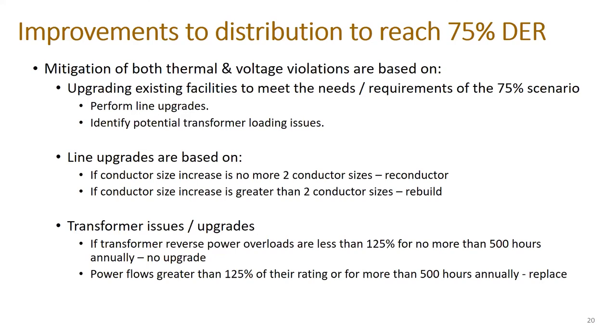And the way we defined the line upgrades or the mitigation techniques was as follows. If a conductor size didn't have to increase any more than a couple of conductor sizes, we said that line could be reconductored. That is, the physical infrastructure of the distribution system could accommodate a slightly larger conductor size. If, on the other hand, it had to be more than two conductor sizes, we were going to have to rebuild that entire line. There's a pretty appreciable difference in cost associated with those two scenarios.